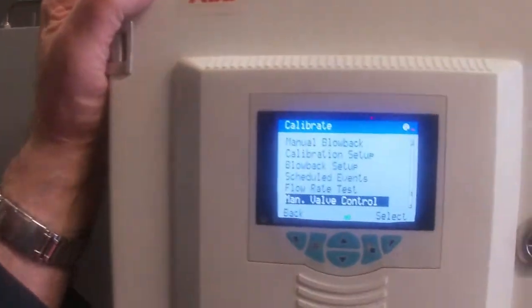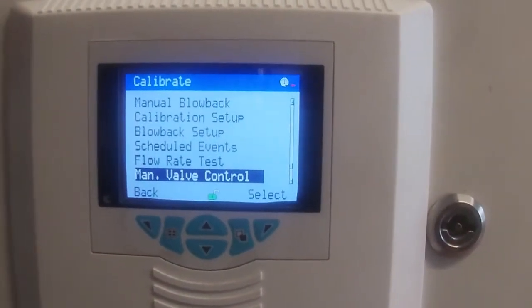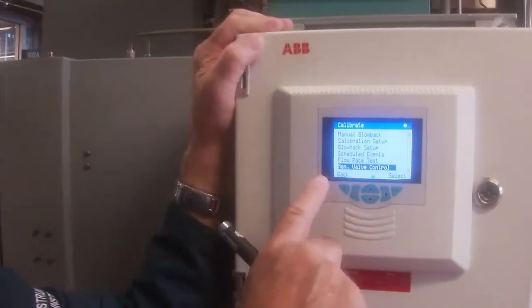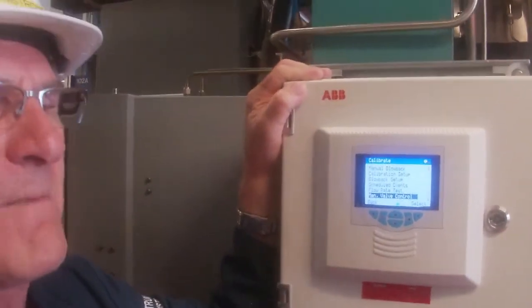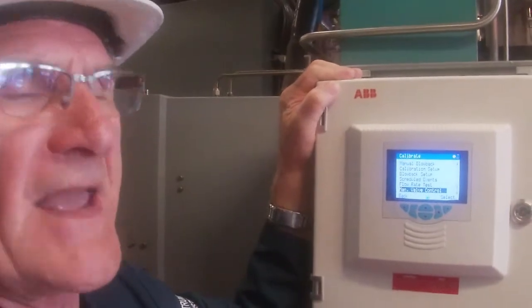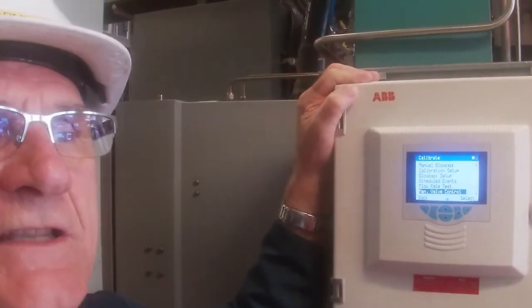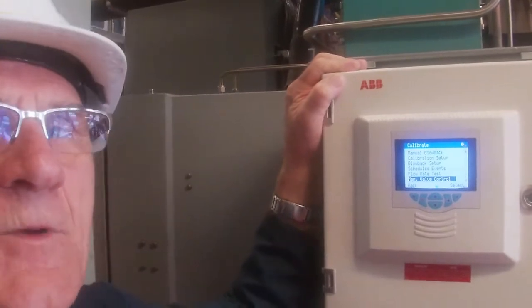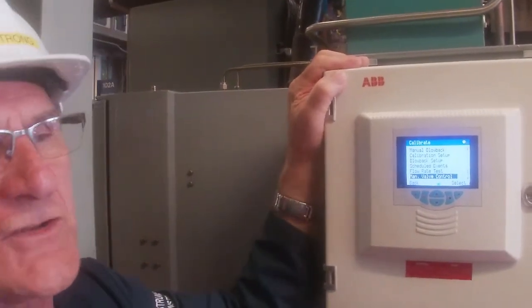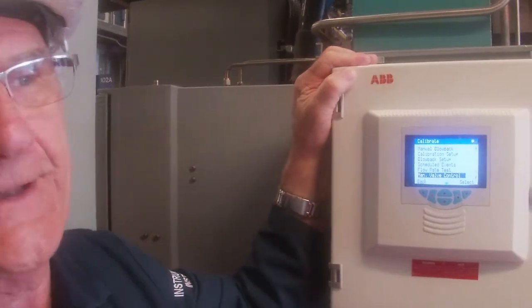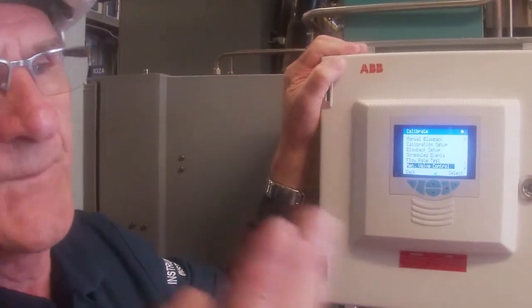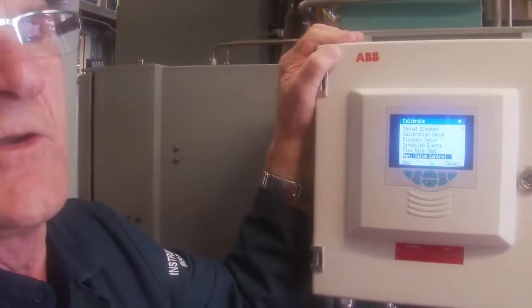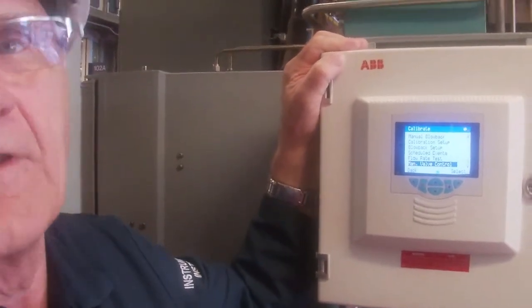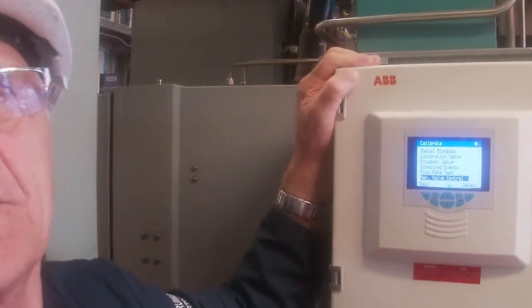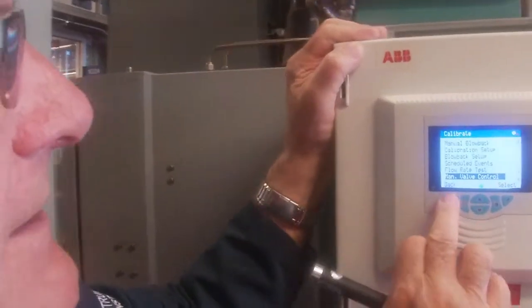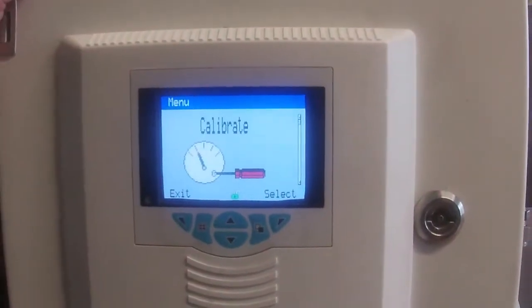And then manual valve control. We're going to use this right at the beginning. I want to take an as-found test. To take the as-found test, we're actually going to manually put in some zero gas, manually put in some span gas, and see what it reads. So that's an as-found calibration. That way, when we've finished our calibration, we can go back to the operator and say, hey, when it was reading 3% O2, it was really 3.5 or 2.5. So your values are going to change a little bit because it was out of calibration. We go back and we're basically exited back out of there.